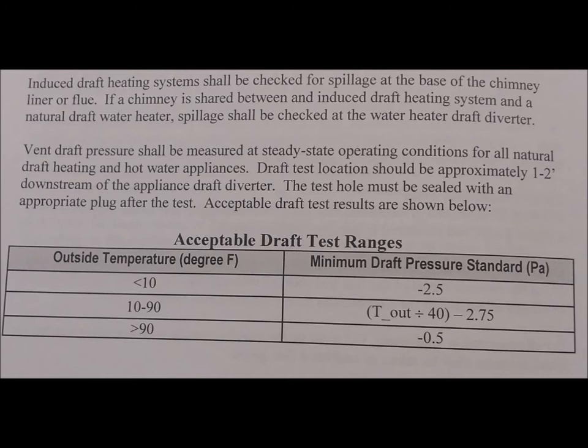Spillage and Draft Test. When a chimney is shared by multiple appliances, the appliance with the smallest BTU input rating shall be tested first, with remaining appliances tested in order of increasing input rate.